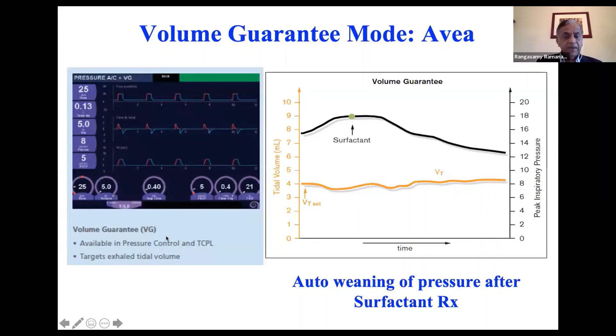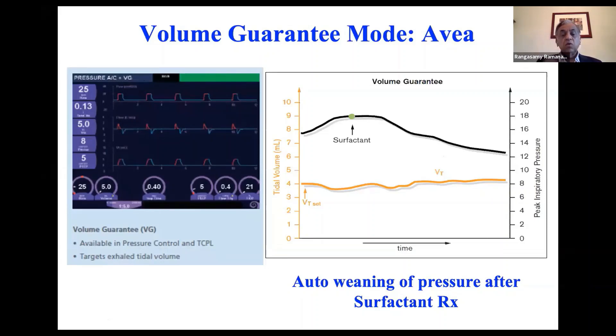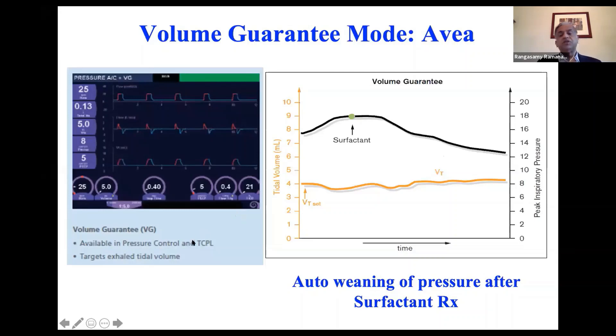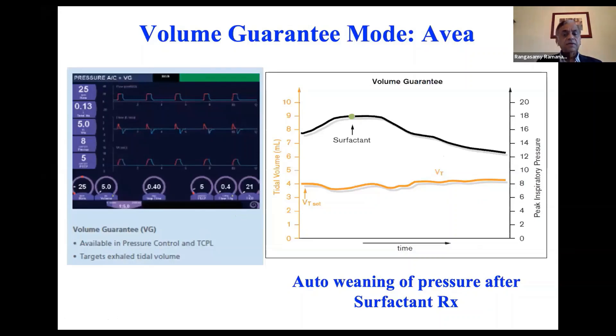You can set it up either in pressure control plus VG or assist control plus VG mode — you can do both. There are subtle differences between the two. We use TCPL plus VG, but if you're used to assist control, you can use assist control plus VG. There's no difference in terms of outcomes.